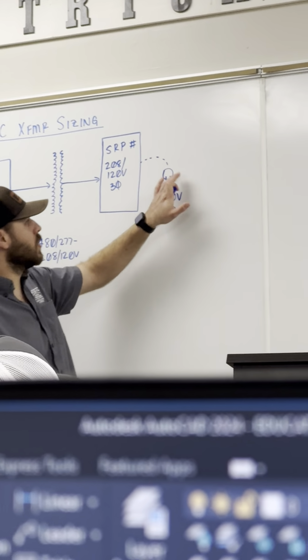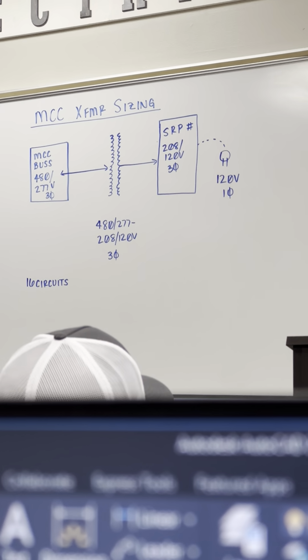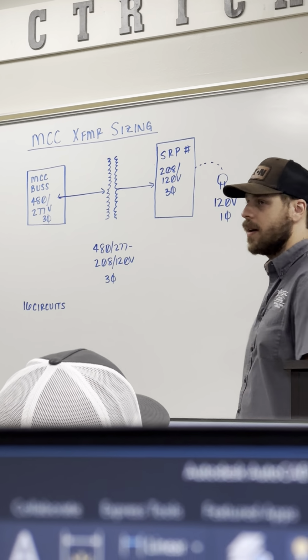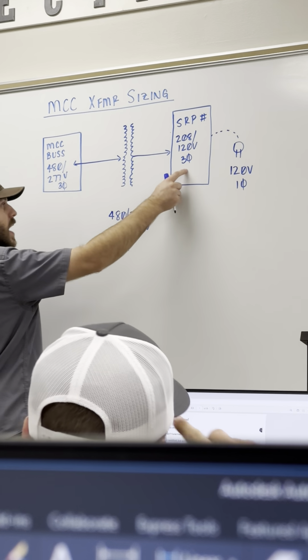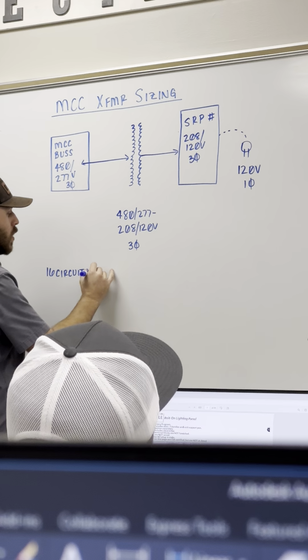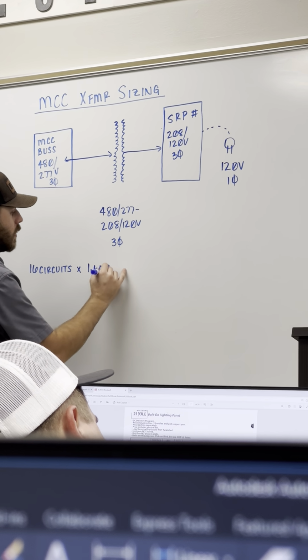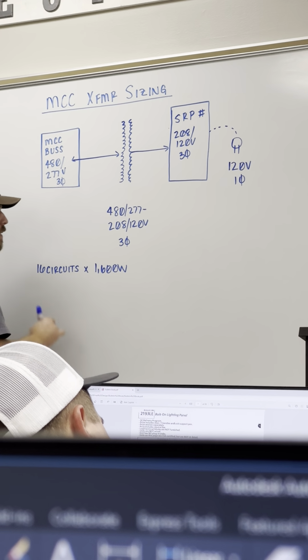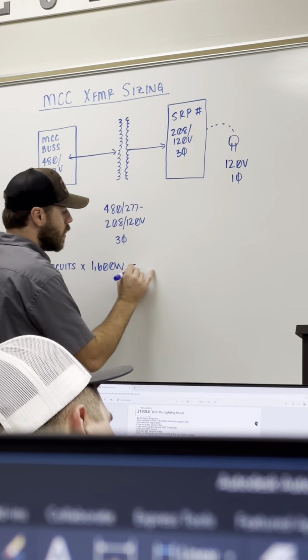well, what's the maximum load in watts that those receptacle circuits can have for our project? You put 4 outer wall receptacles or you put 2 machine mounted receptacles together, what's the wattage on that you can't exceed? 1600, right? So we'll size, again, everything for the maximum. So we'll take 16 circuits, which is the max number of circuits that this panel can hold. We're going to multiply it by 1600 watts, which is the maximum a circuit can have. So when you do 16 times 1600, what do you calculate?